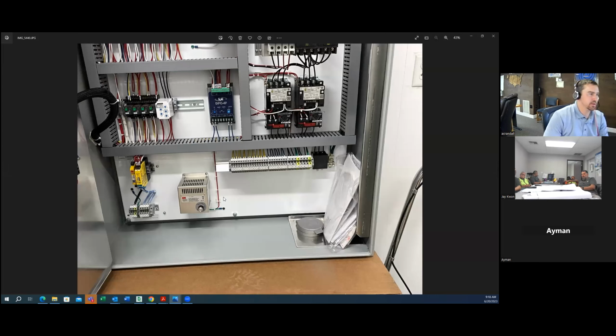Well, in this one, level sensing will come up into the bottom of the control panel on the left side. And then your cables for pumps come up into these terminals on the right-hand side. So that's one thing to note, just so you're not crossing conduits, coming up in a weird spot and having to cross cables. Does that make sense?